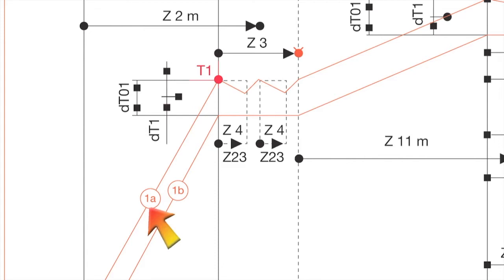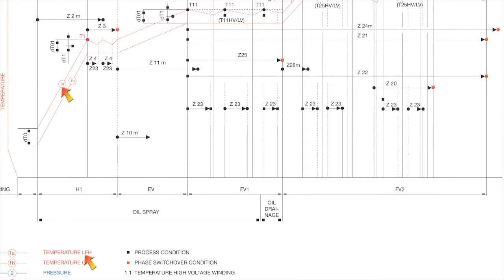A few degrees, DT1, normally 5 degrees, before reaching T1, the system will measure the temperature in the HV winding and calculate the temperature in the LV winding. If the temperature in the HV winding is much lower than the average winding, the converter will heat the HV winding separately if this is selected on the start screen.